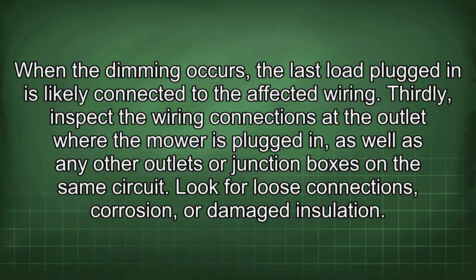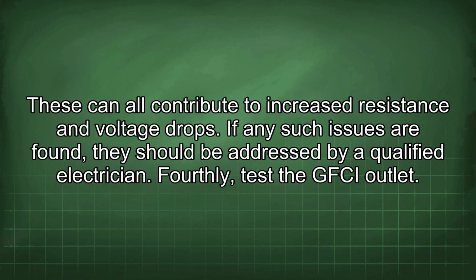Thirdly, inspect the wiring connections at the outlet where the mower is plugged in, as well as any other outlets or junction boxes on the same circuit. Look for loose connections, corrosion, or damaged insulation. These can all contribute to increased resistance and voltage drops. If any such issues are found, they should be addressed by a qualified electrician.